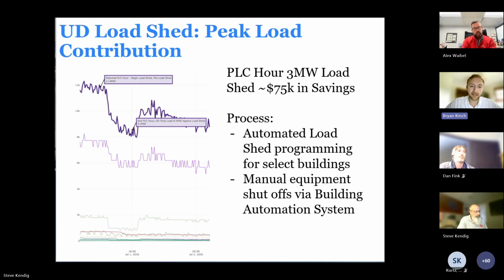I wanted to highlight the peak load contribution a bit more. UD has what I would describe as a very good load shedding scheme. Whenever we know there's going to be a PLC hour, we target between 3 and 4 megawatts of load shed. We do this through automated load shedding programming with 4 different levels that trigger, and we usually trigger all 4 for a PLC day. Then we go through and do manual shutoffs via the building automation system, mostly through Metasys.